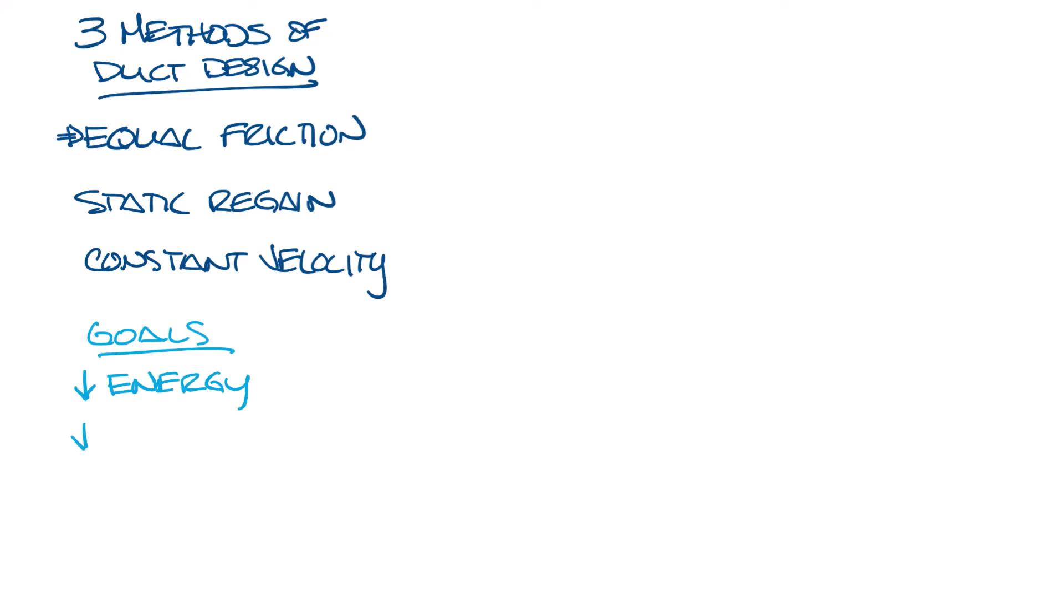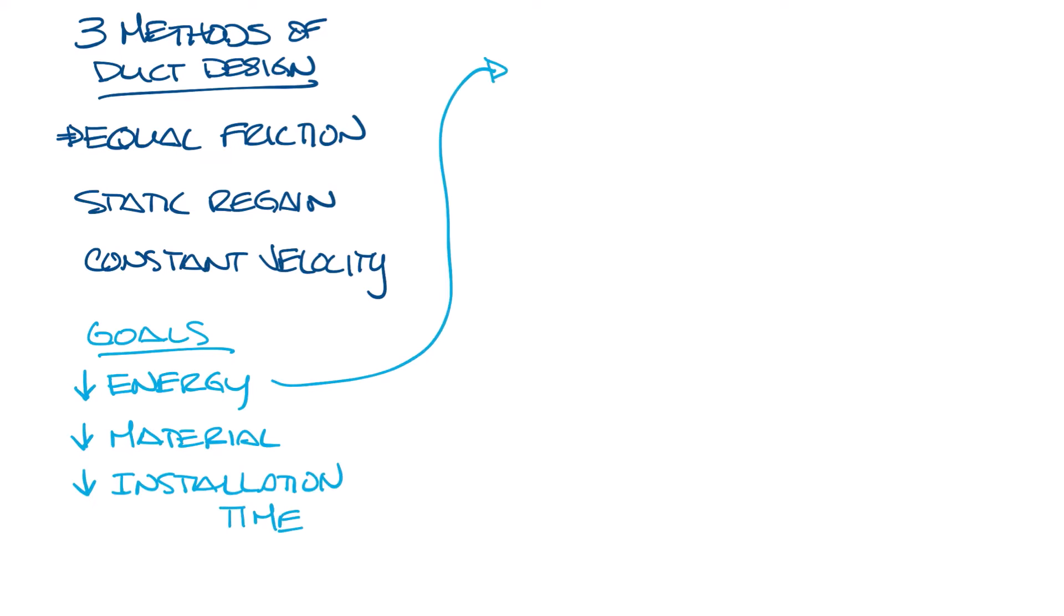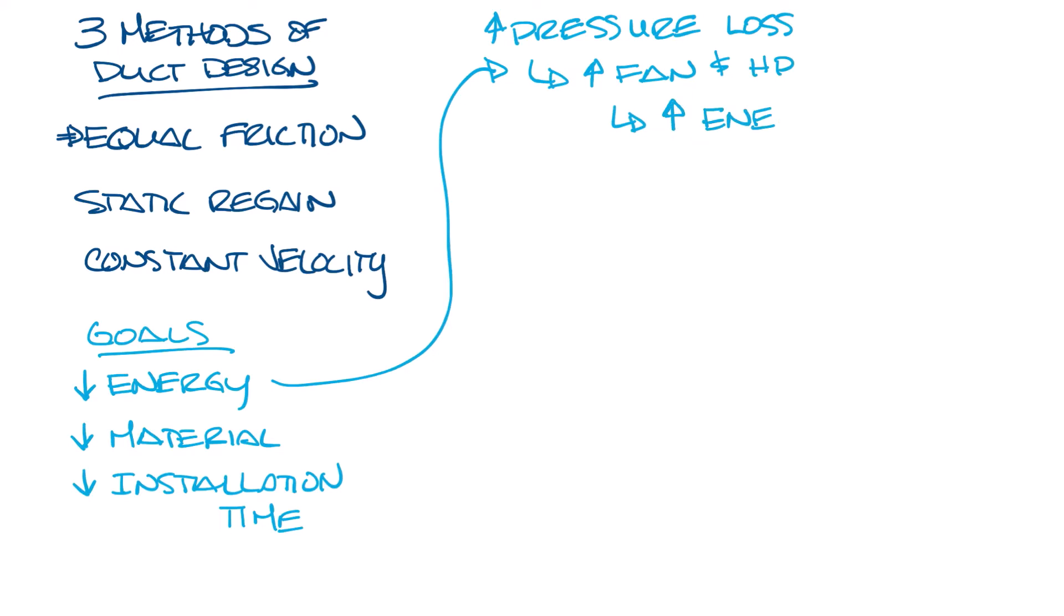When we design a duct system, we want to minimize energy usage, material, and installation time. Energy usage is a function of pressure loss. The higher the pressure loss, the bigger the fan and motor horsepower that will be needed to get the airflow through the system and out to the furthest zone, so this means more energy used in the system.